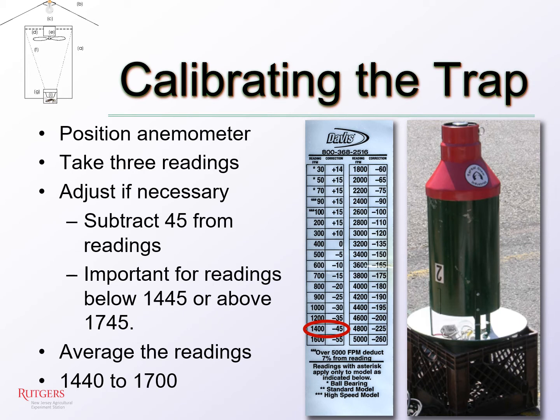These adjustments are provided by the manufacturer of the dial anemometer and are important primarily for reading under 1445 or for readings above 1745. That's because at those readings your light trap may be out of the appropriate range of 1440 to 1700 RPMs. Average your adjusted readings, and if your light trap is properly running, the average will fall between 1440 and 1700 RPMs. But what happens if these readings are out of range?